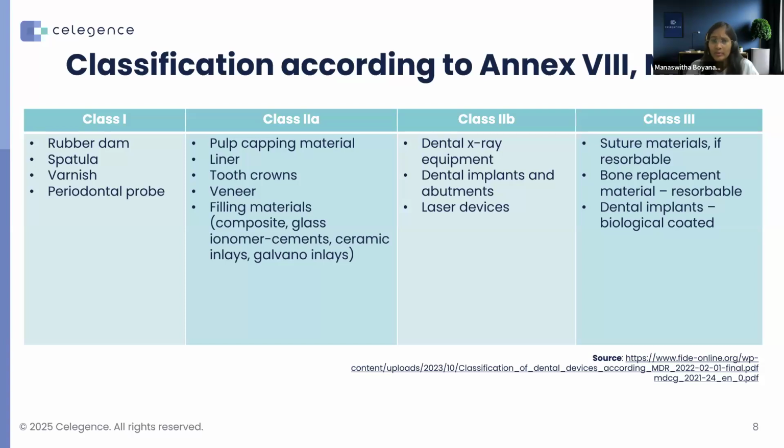Products such as resorbable bone materials, cements, endodontic filling materials, including a drug, or even animal-derived bone graft substitutes all fall into the highest risk class, class 3. Further, all devices that contain nanomaterials are classified into the highest risk class.